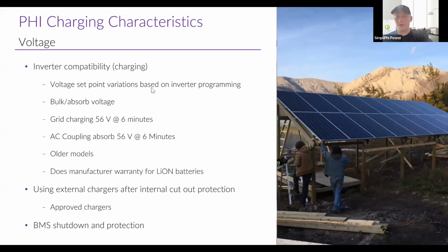If you're going to be using an inverter charger, I would definitely recommend checking that it has, firstly, the low battery cutout set point that is required to be 48 volts or higher. And I would check that they actually warranty their product for use with lithium batteries. If they do not warranty for use with lithium batteries, that should explain right there that maybe it's not the best fit.